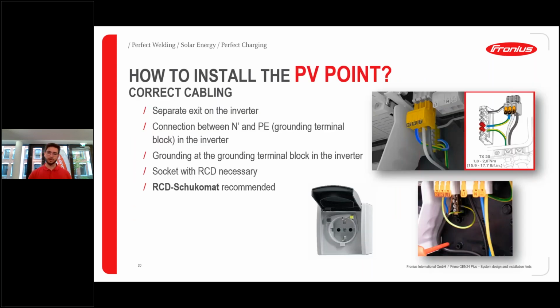Yeah, I quickly want to give you a closer look at how the installation looks. It looks a little bit confusing at first sight, but on top here we can see this connection compartment, again our single phase plug. And first of all, the naming: it states here 2 neutral with an apostrophe above it, and also a phase L1. Why do we have here 2 neutrals?